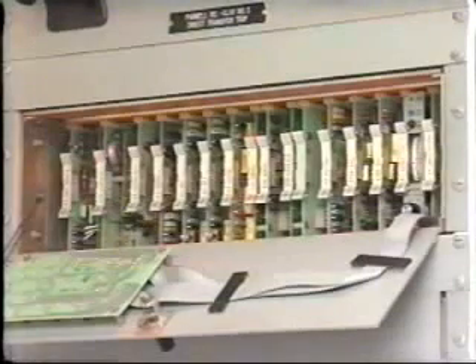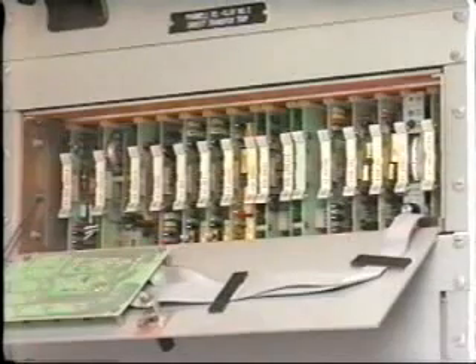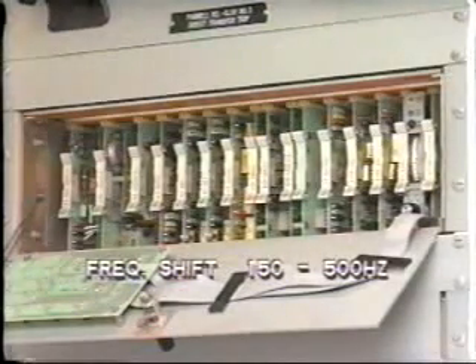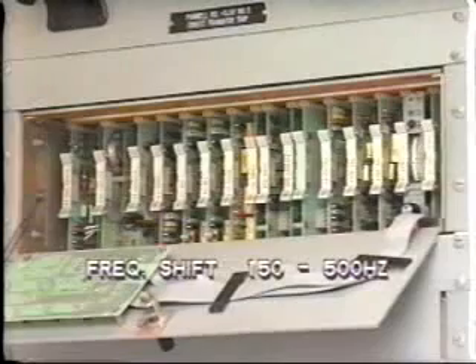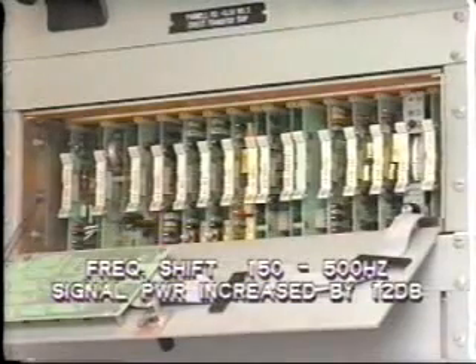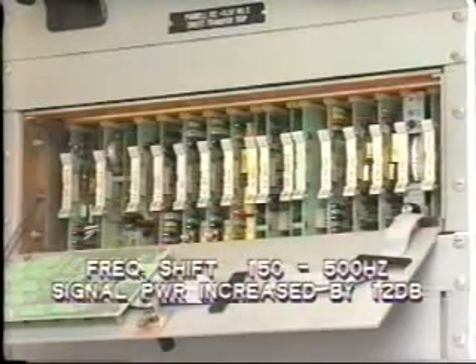Where the signals are transmitted by an audio tone system, the operation is similar. The shift in frequency is within the range of 150 to 500 hertz, and the signal power is increased by 12 dB.